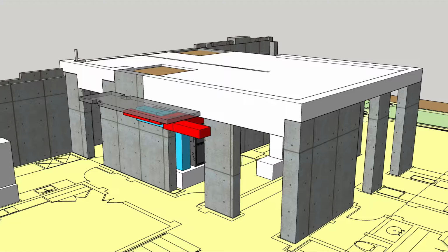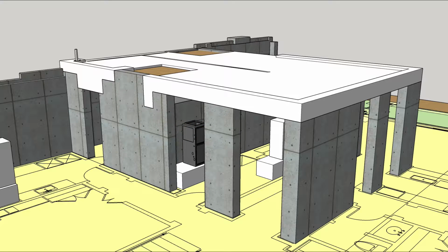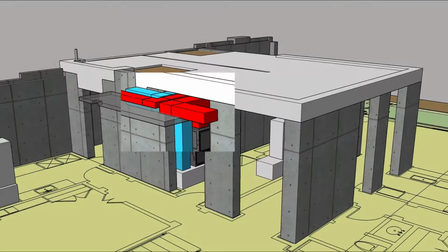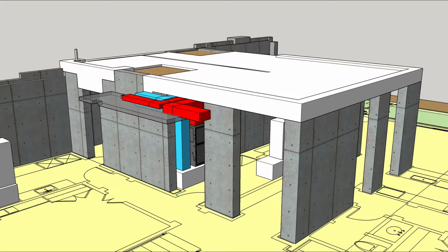Knowing that the plans contained this hidden problem, we approached the structural engineer to devise a solution. The engineer looked at the loads on these beams and determined that the structure would work with those beams being only 18 inches deep, as our modified model shows here. Shallower beams allowed the ductwork to be raised to a point where it was above the ceiling height. By having this model of the project, this issue was recognized in advance and resolved with no lost time, architectural compromises, or additional cost to the budget incurred.